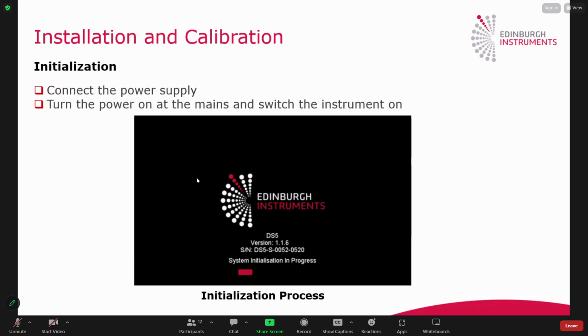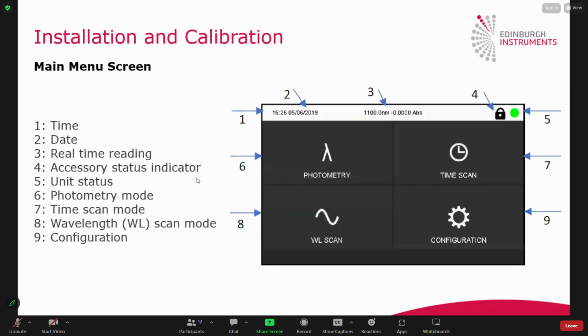Then the instrument will start the initialization process. It looks like the screen here, and it will take about 10 to 15 seconds. Then after the self-initialization, you will see a main menu screen like here. On the top left-hand corner, you will see the time and the date. And in the middle, you will see the real-time readings. And on the top right-hand corner, you will see the accessory status indicators. There's a padlock and also a green circle, which means the unit status. The green circle means the unit is healthy and good and there's no error.